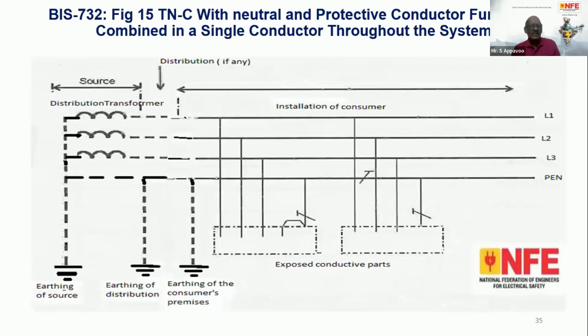As per regulation and standards, suppliers are empowered to have a TN-C, that is, the neutral as well as the protective earthing conductor combined in a single conductor, because they can't provide a sturdy earthing conductor all the way to the consumer premises. So as far as the suppliers or distribution companies are concerned, they can provide a combined system up to the consumer premises. It is the consumer's responsibility to connect his installation. By means of these parallel electrodes, the supplier gets the least resistance value.